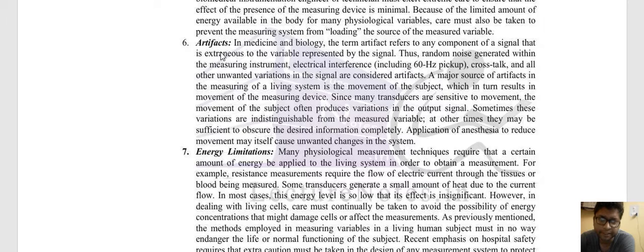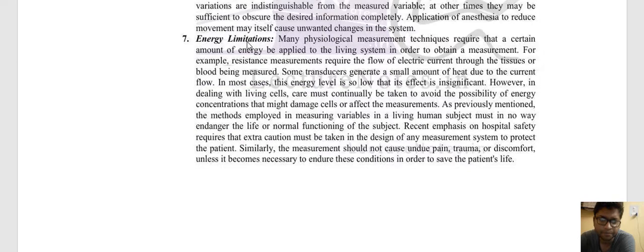The next one is the artifact. In medicine and biology, the term artifact refers to any component of a signal that is extraneous to the variable represented by the signal. Thus, random noise generated within the measuring instrument, electrical interference including 60 Hz pickup, crosstalk, and all other unwanted variation in the signal are considered artifacts. A major source of artifact in measuring of a living system is the movement of the subject, which in turn results in movement of the measuring device.